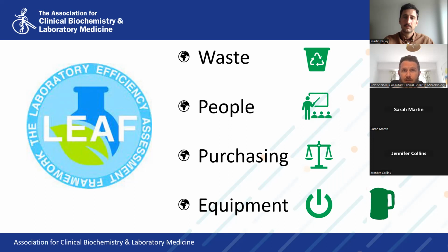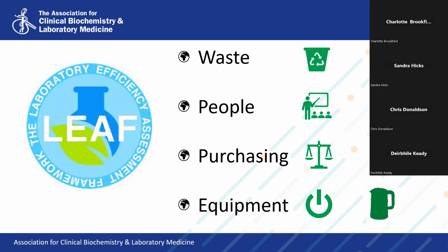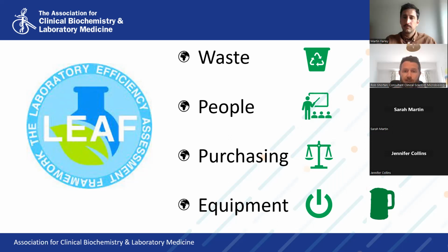So we've adopted this green kettle symbol, which we now have printed and stuck on every bit of kit in our laboratory that can be powered off when not in use. It says it's safe to do this. So for example, we contacted Bruker and said, can we power down our MALDI overnight? And they said it will affect the vacuum, it will affect the calibration, it's likely to need more work more often. So we made a pragmatic decision that that was a piece of kit that has to stay on 24/7. So I'd encourage you to go around your lab and look at these things systematically and ask, what's on all the time that doesn't need to be on all the time.